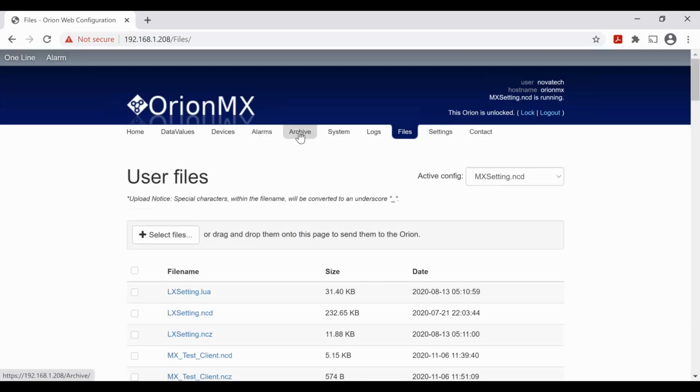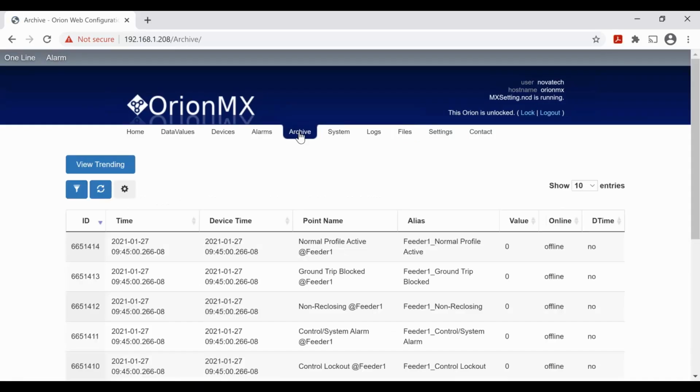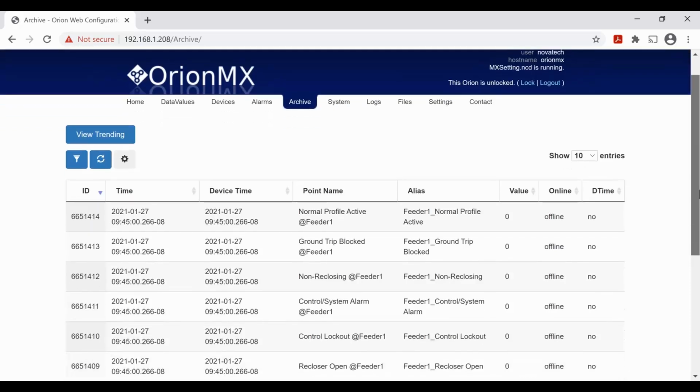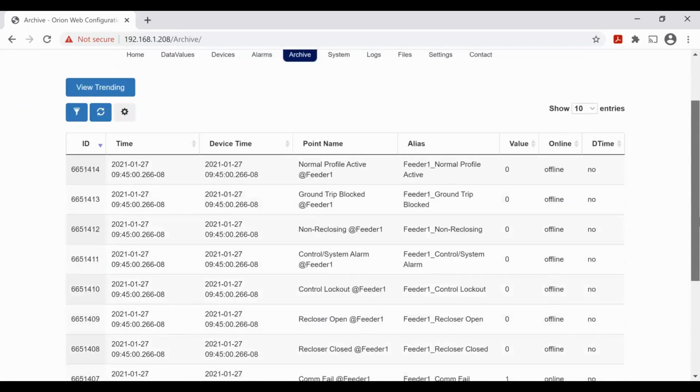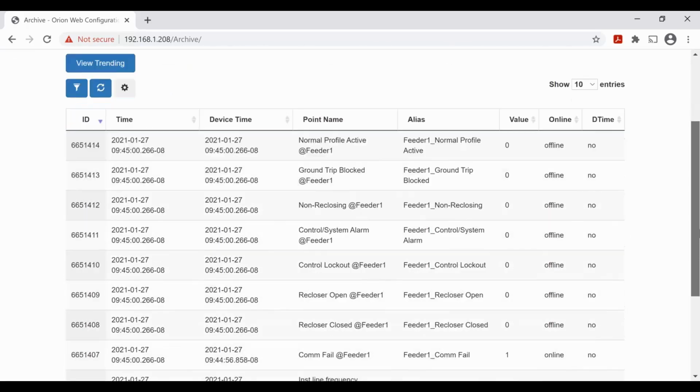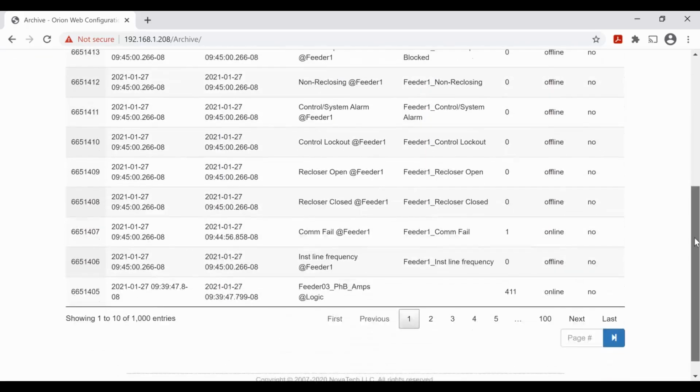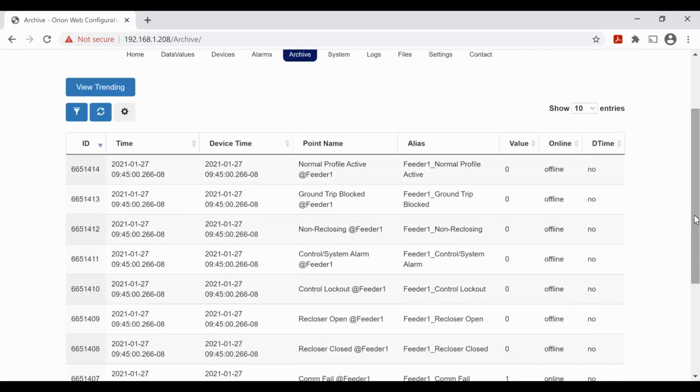All right, so go to our archive tab now. Just to review, the alarms and archive tabs won't appear unless you enable the Postgres database, as Sean showed at the beginning. Similar here, this is your archive database. Anytime a point in your archive changes, say every 15 minutes if you configure it to be timed, or every time it passes the dead band, it gets archived.